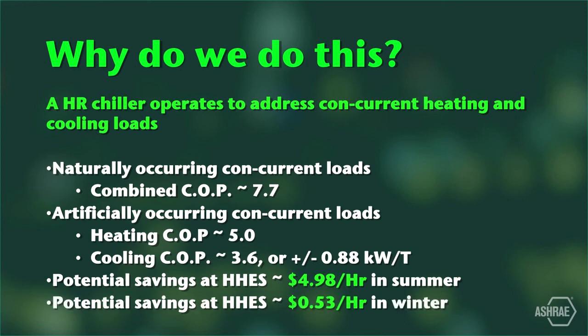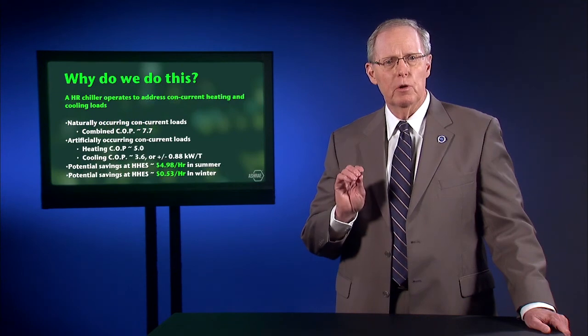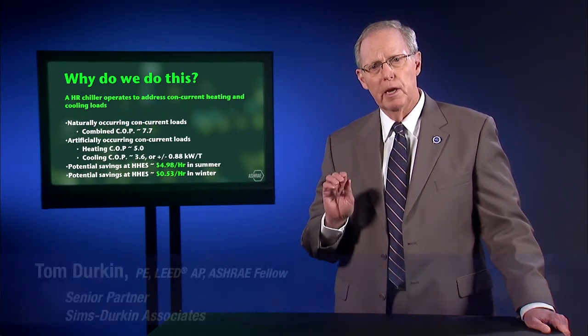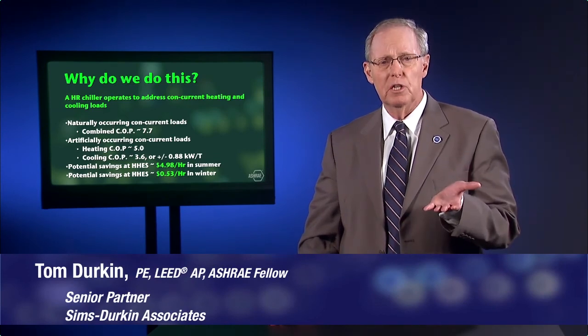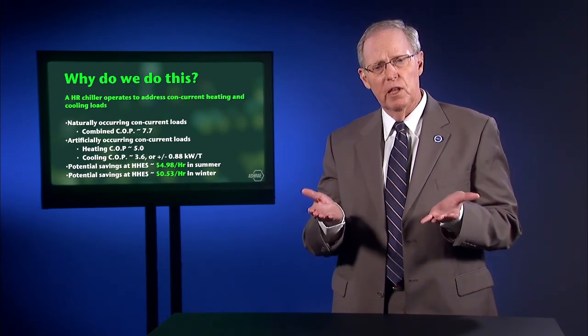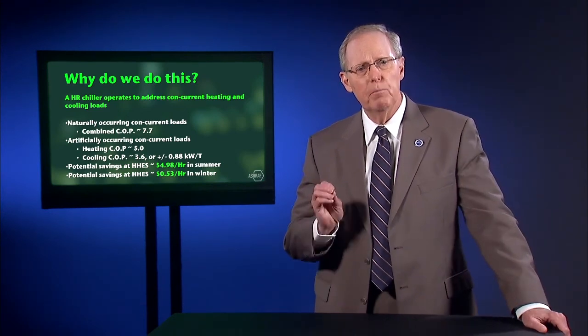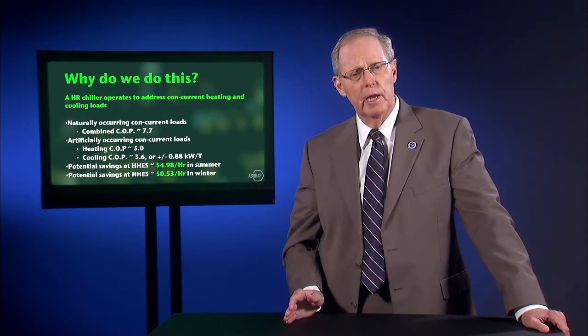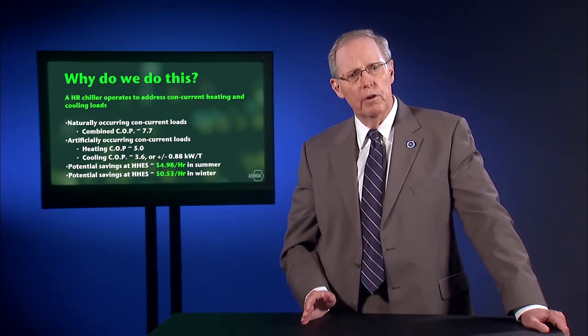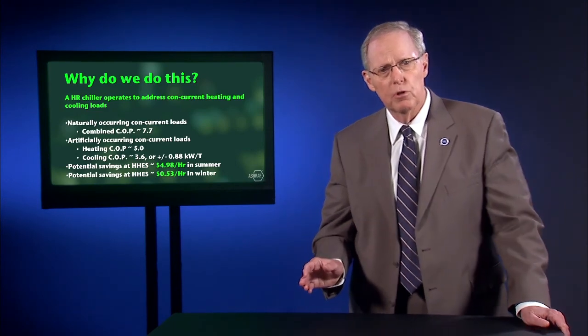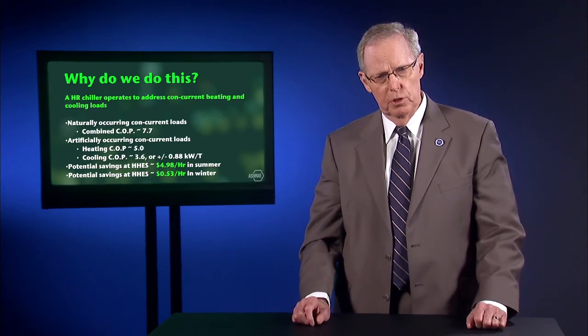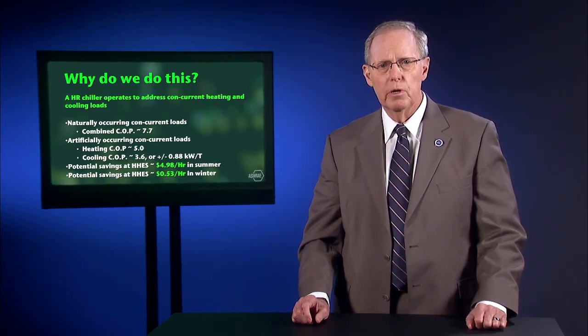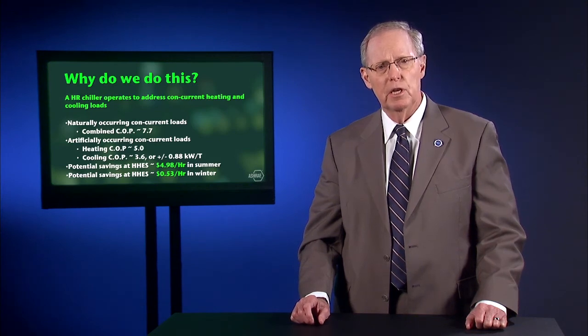Conversely, artificially creating a cooling load with the relief air handler to load up the heat recovery machine will save energy and may save money instead of running the boilers, a COP of around 5. Now, that would require a site-by-site utility rate analysis, but at Hamilton Heights, if gas costs more than 60 cents a therm and electricity costs less than 11 cents a kilowatt hour, then we save money by running the heat recovery chiller for winter heating and using the relief air handler to artificially cool the relief air. Now, smart controls are an obvious and critical piece to the solution. The heat recovery chiller operation needs to be coordinated with the boiler and the chiller to maximize efficiency and savings.